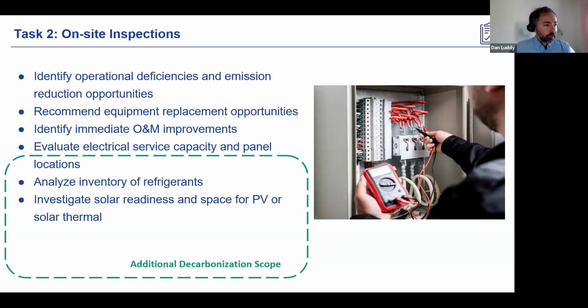The bottom three bullets in the green circle are what we're additionally adding for an emissions reduction audit: evaluating the electrical service and panel locations so we're aware of where there might be capacity to add additional loads, whether EV chargers, tie-ins for on-site renewables, heat pumps, or other electric-based heating systems. It also includes an inventory of refrigerants and refrigerant-containing equipment, and an investigation of solar readiness and space for renewables on site.